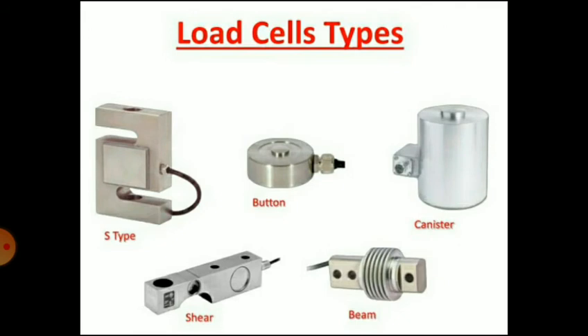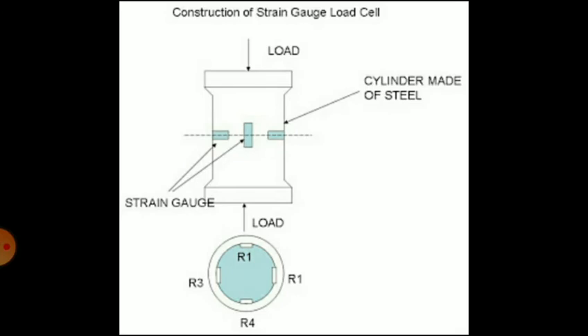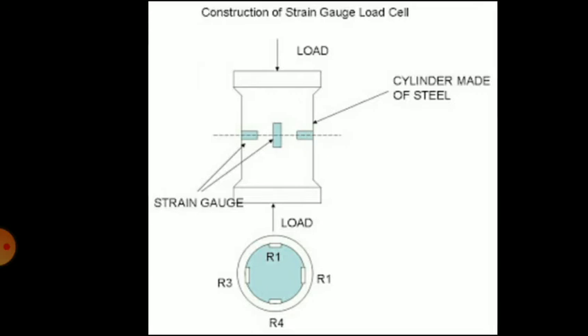So these are the load cell types: button, S type, beam type, and shear type load cells, shown in this slide. Now the construction of a strain gauge load cell. You can see there is a cylinder made up of steel. At the bottom there is a top view, and at the top the front view is shown, and the position of the strain gauges attached to the cylinder is shown in a diagram. You can see 4 strain gauges that are attached.